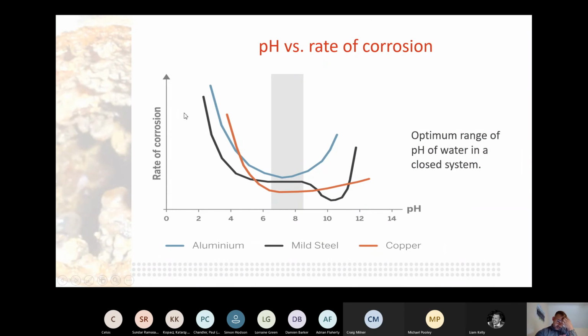This graph is a new one we've recently added, referring back to what I mentioned a couple of slides ago about pH environments. You've got the grey block down the middle of the graph between 6.5 and 8.5 pH - that's generally referred to as the neutral zone, the habitat in which all metals can cope. Different inhibitors provide different pH buffer ranges.